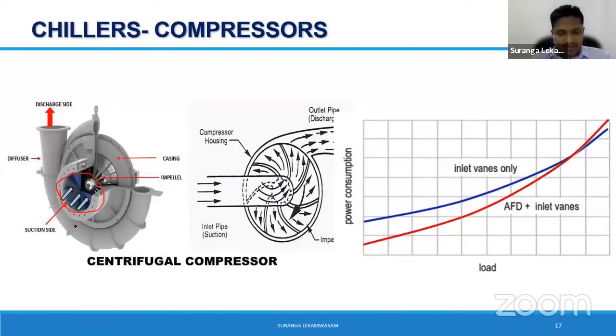It's kind of a throttle in action. You can use it to achieve stepless capacity controlling of the centrifugal chiller. Efficiency-wise, when you compare a variable speed drive with inlet guide vanes versus inlet guide vanes only, you can see the efficiency is much better in the first option, VFD plus inlet guide vanes. Efficiency is compromised a bit if you only rely on inlet guide vanes. So these are all things you need to look at when you define your chiller.